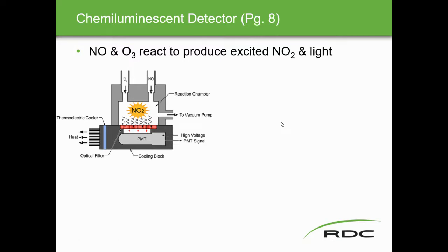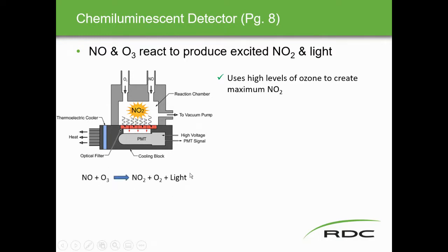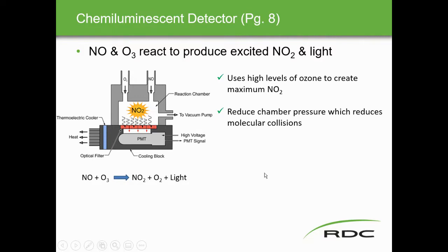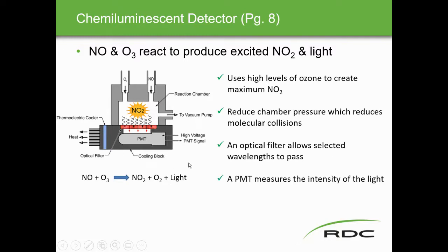Nitric oxide and ozone react to produce excited NO2 and light. The emitted light is picked up by the photomultiplying tube. High levels of ozone are used to create maximum NO2. The reaction: NO + O3 → NO2 + O2 + light. The reaction chamber operates under reduced pressure — a small vacuum — to reduce molecular collisions. An optical filter allows select wavelengths to pass, and the photomultiplying tube measures light intensity. That intensity corresponds to the concentration of NO2.